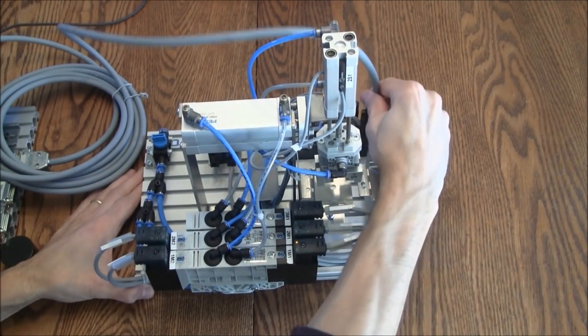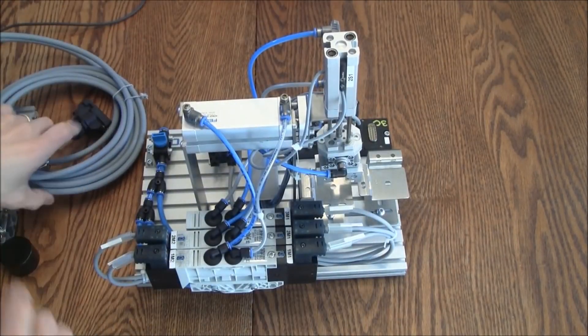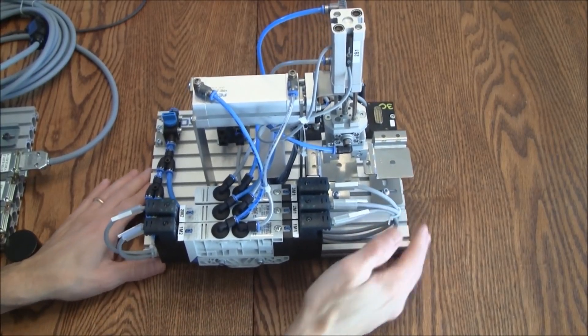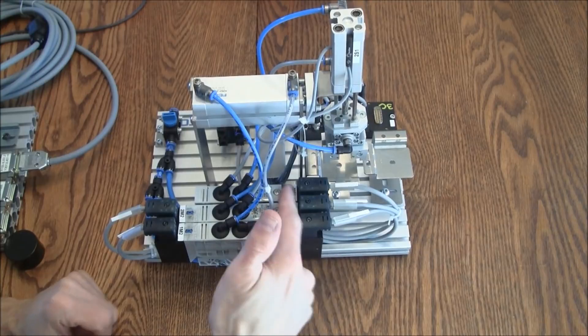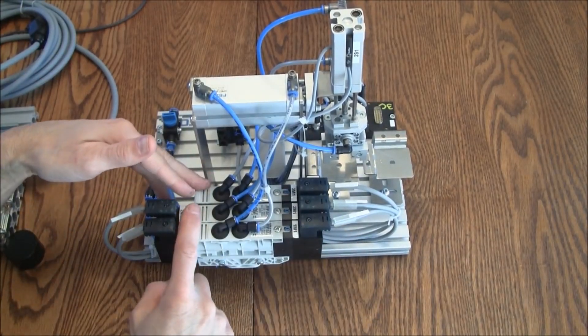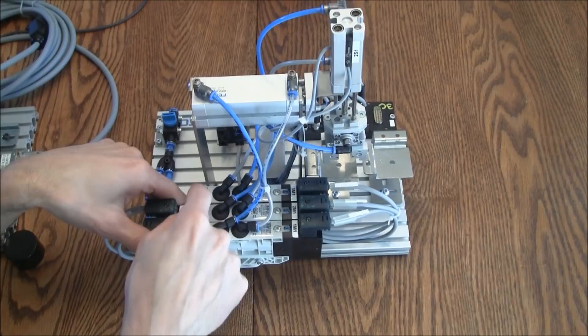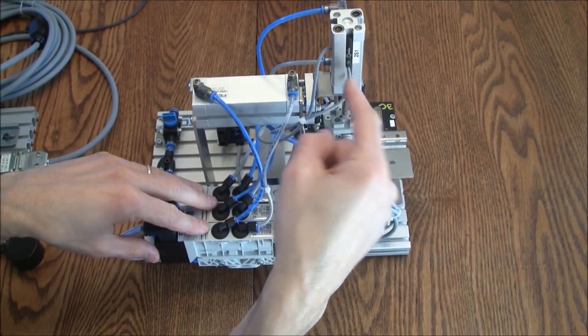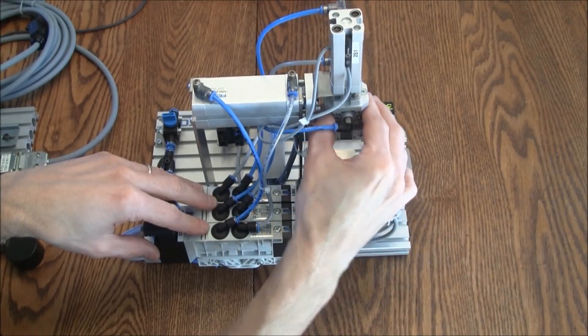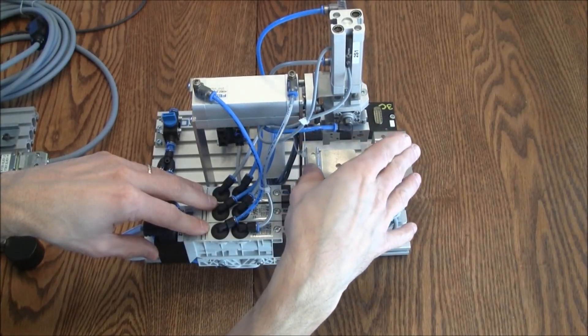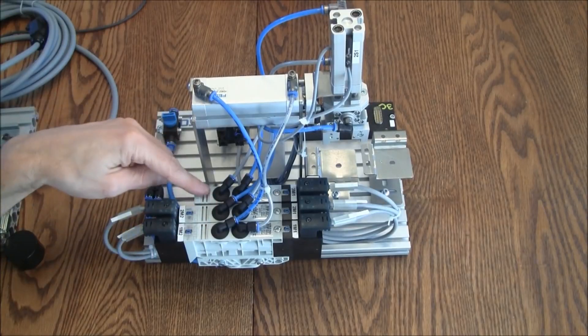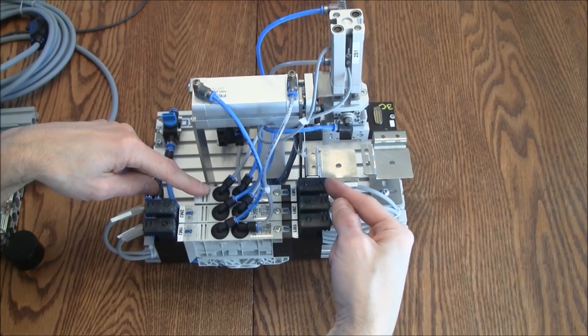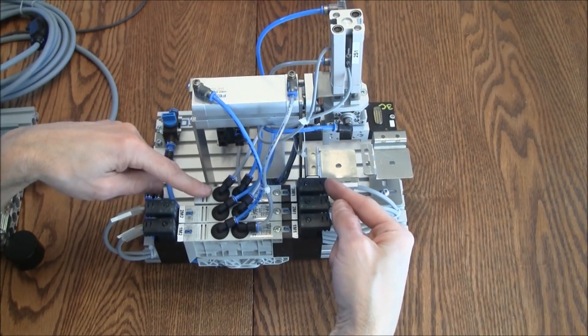You'll also see that we have valves. The valves are mixed. We have one that looks different from the other two. But we do have a total of three valves because we have three cylinders: the horizontal, the vertical, and the gripper is also a pneumatic cylinder. No sensors on it but it is a pneumatic cylinder. One of those cylinders is being controlled by this valve that has a single solenoid on it. It is a four two-way valve.